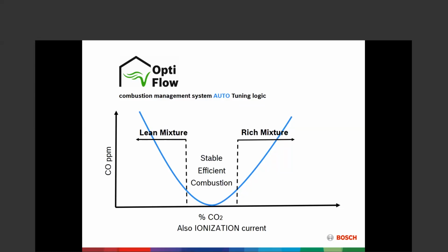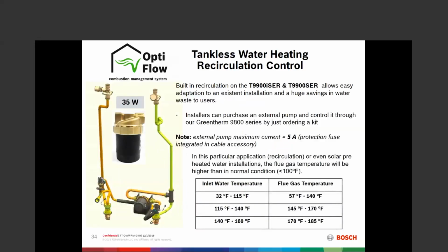It's going to optimize the combustion efficiency. So we can always talk about thermal efficiency, but that's optimizing combustion efficiency. And then as we talk about why we want the unit to control domestic recirculation, well, we want that because of the relationship between the inlet temperature of the water and the flue gas temperature. As the water starts to come back to the unit hot, if we add between that 15 and 25 degrees onto that, then our stack temperatures can rise to dangerous levels, or potentially dangerous levels, on PVC. So we're going to allow the unit to manage that.